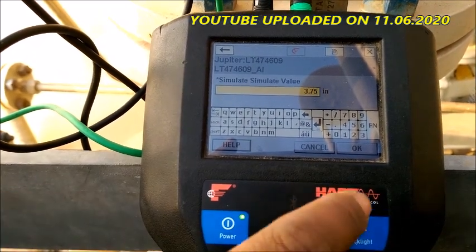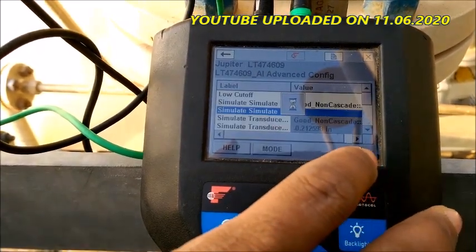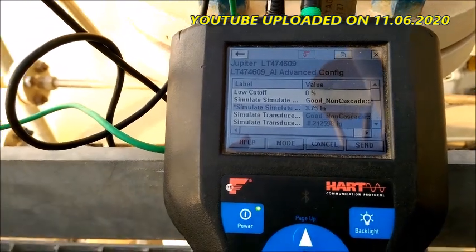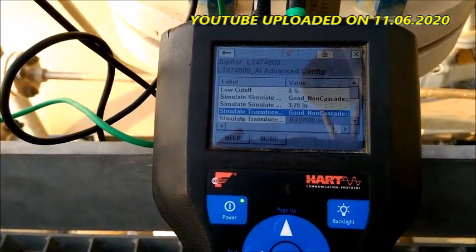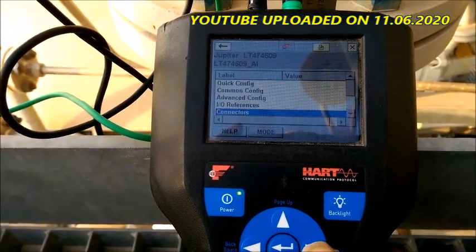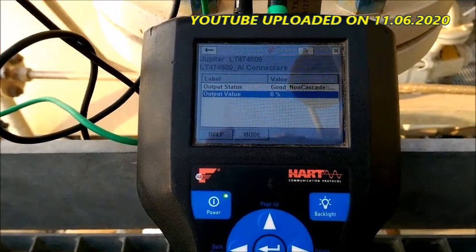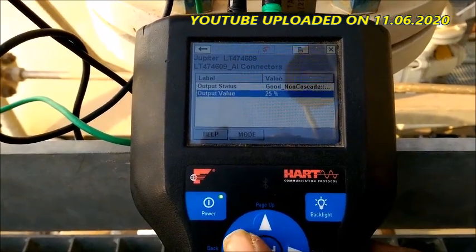Now I apply for 25 percent — that is 3.75 inches. It is showing 3.75 inches, so it should come to 25 percent level. You can see the 25 percent.